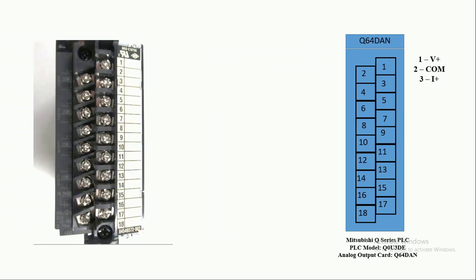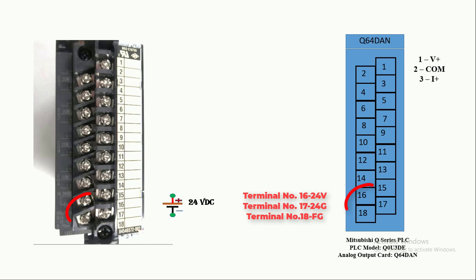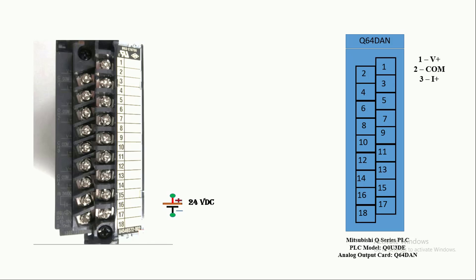Look at the connection terminals for the analog output card, where there are three connection terminals for each channel from which we can get both voltage and current signal of different ranges. For hardware connection, first you have to power up the analog output card with 24V DC power supply. Connect the positive terminal of the power supply to terminal number 16, and the negative terminal to terminal number 17 of the analog output card.